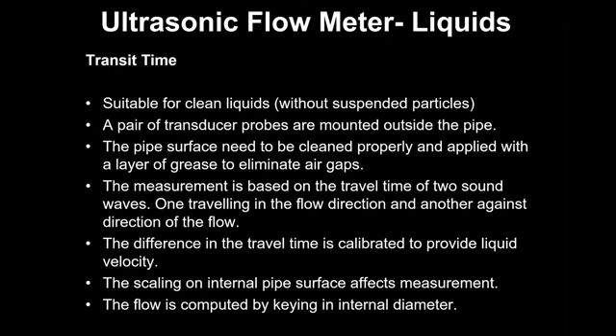So the difference between these two signals, one going against and another going along the direction, means there is going to be a difference in the travel time depending on the velocity of the liquid. You can imagine that the difference would be very small. The diameter is small, everything is small. So how accurate the instrument has to be, that is basically the trick of that instrument. It is maybe in nanoseconds or whatever, that is the kind of difference you are going to get. And based on that, it will calculate the velocity of the liquid.